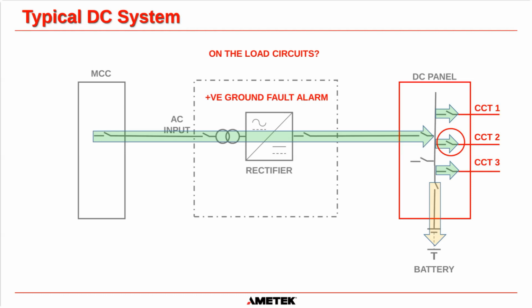And just to check, I would always double check. I would then move on to circuit three. I would open that, and then the fault would go away because that's what we've determined. It's on circuit three.